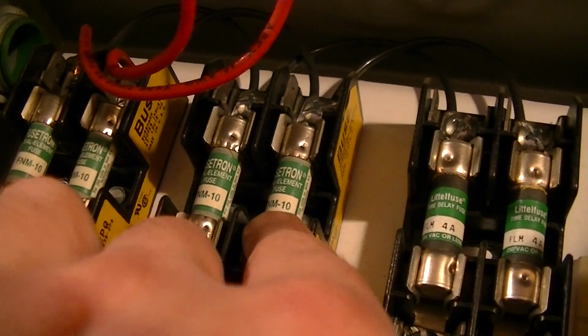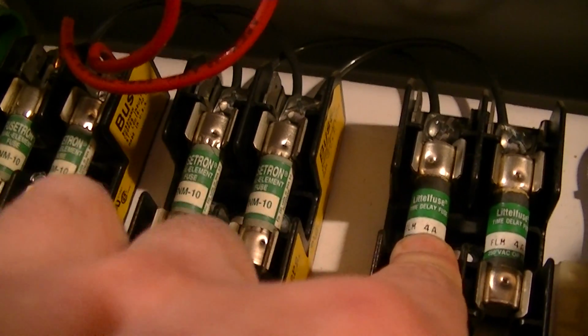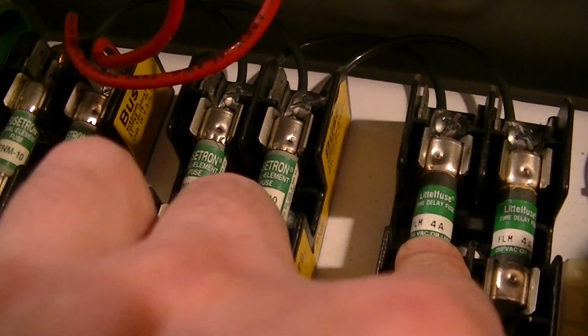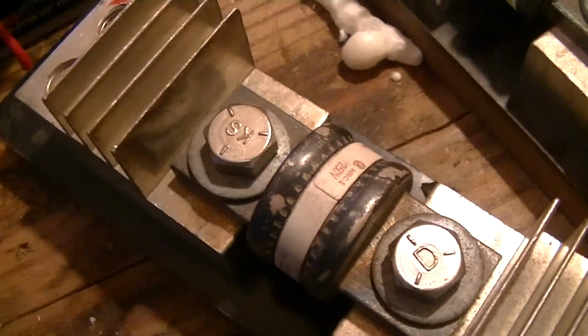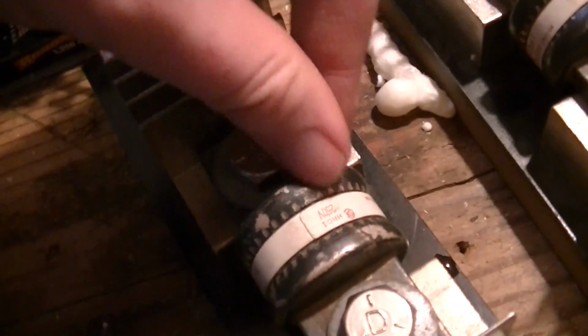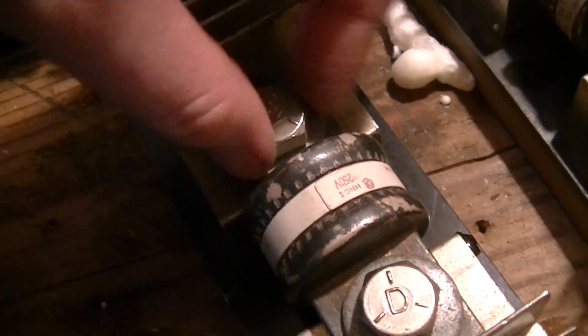And this is a very good practice to do, is with these cartridge fuses, put them in so that you can actually read what the legend printed on the fuse is, because oftentimes you'll see something like these, which are some battery protection fuses I got for the solar farm, but these fuse blocks came with the fuses. Whoever put the fuses in didn't put them in so that you can read the legend.